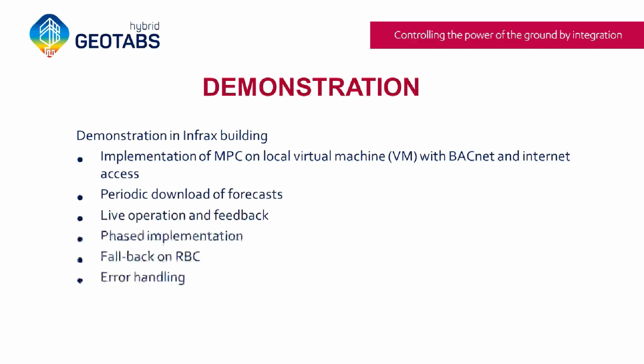So just to give you a bit more detail on that, for the actual demonstration we did an implementation of our algorithms on a virtual machine in a Linux environment. And this machine can directly write on BACnet. It also has internet access for fetching weather data, with a periodic download every 15 minutes of new weather forecasts. And the idea is that every second we read BACnet measurements and then do closed-loop control. For instance, if we have some PID controls for tracking set points, we operate those at a faster update rate than the weather forecast. So there are separate algorithms.